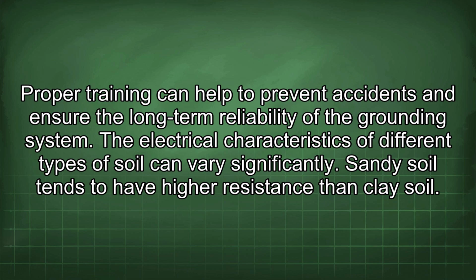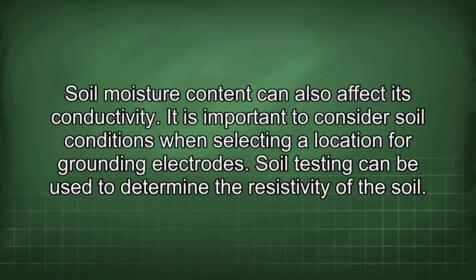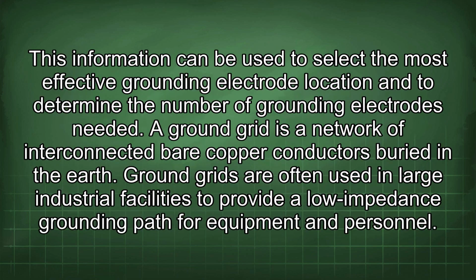The electrical characteristics of different types of soil can vary significantly. Sandy soil tends to have higher resistance than clay soil. Soil moisture content can also affect its conductivity. It is important to consider soil conditions when selecting a location for grounding electrodes. Soil testing can be used to determine the resistivity of the soil. This information can be used to select the most effective grounding electrode location and to determine the number of grounding electrodes needed.